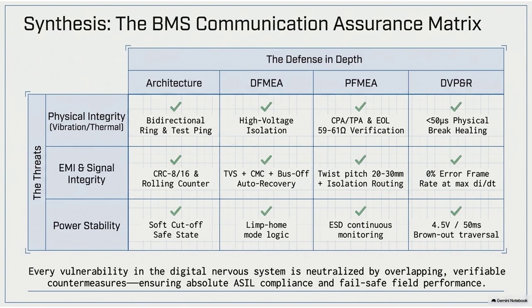But then we saw how the engineering world fights back. We saw the digital immune system: the bidirectional self-healing rings that sense a broken wire and instantly send data backward around the loop, achieving 100% fault tolerance in 50 microseconds. It's just so fast.